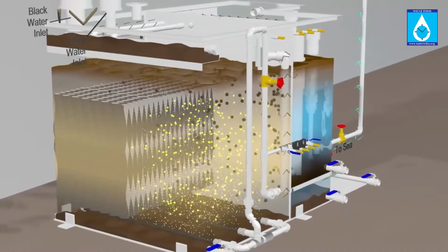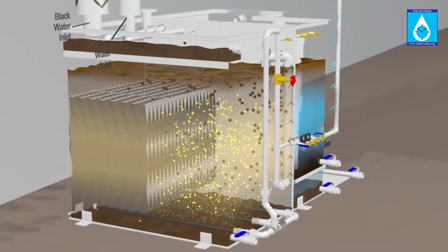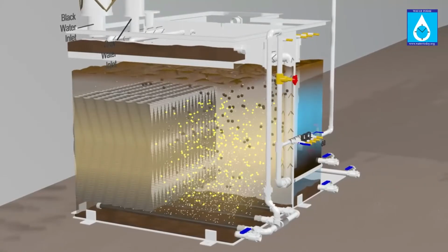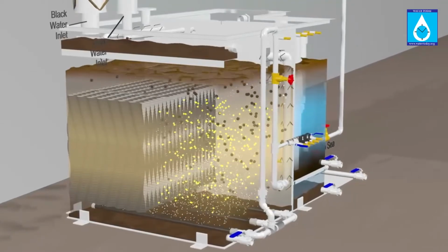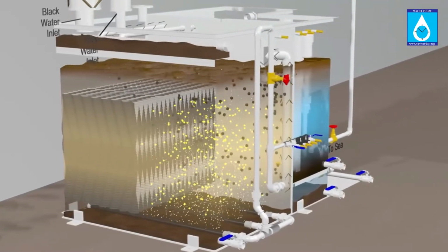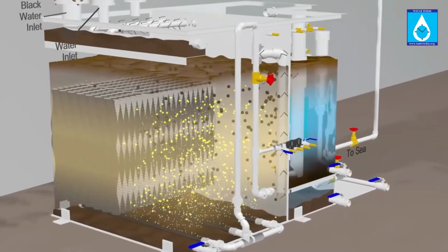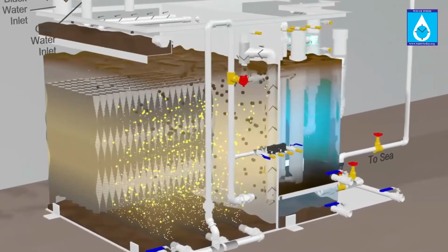But when we go to the site, we see that the pumps are lying down, kept close to the wall, or kept away from the wall, or lifted very high. All these parameters put together are a major cause of failure when it comes to sewage handling. So we will also see how we can handle all this sewage.